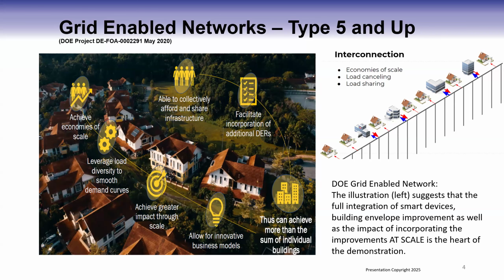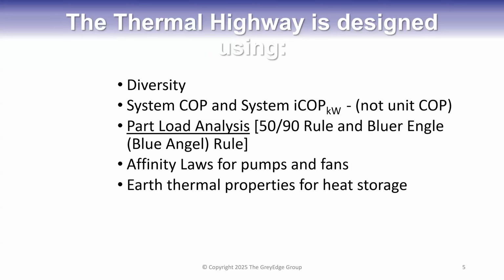The big issue is shaving peaks and time-of-day rates, trying to eliminate or minimize them at best. The systems use diversity; system COP is what we use to measure this. We've come up with a calculation for that—it's not the COP of the unit, it's the COP of the central loop, basically the amount of pumping needed to move the energy, inclusive of diversity and line losses. We use part load analysis, looking at what we really need for the system, because we have a 50-90 rule: 50% of the load will handle 90% of the year. Doing that allows us to maximize the use of this. We'll go into Mesa State, Colorado Mesa University, and Weber State here in a bit.